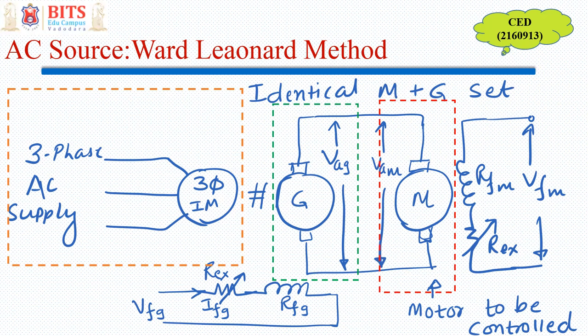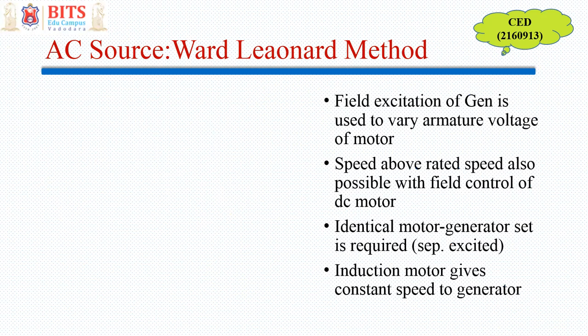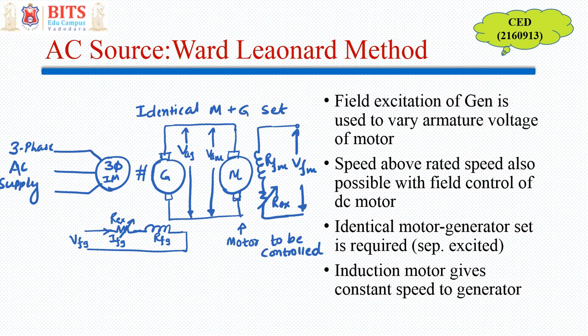In addition, we can have field control also, because this generator and motor are separately excited. The motor also has a field winding, so I can exercise field control if I wish to have speed above rated speed. The field excitation of the generator is used to vary the armature voltage of the motor, and speed above rated speed is also possible with field control of the DC motor.